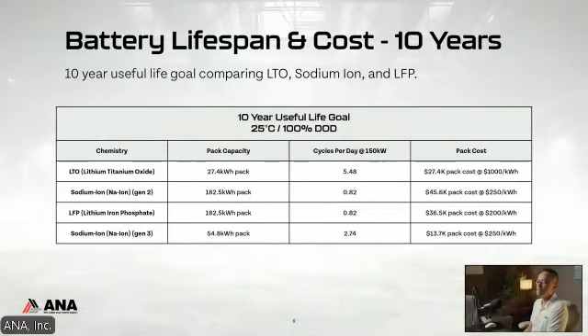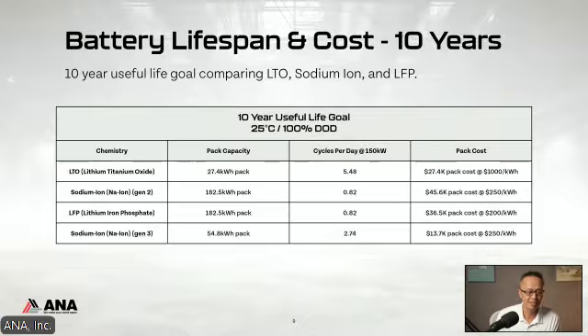In this chart, we're going to look at the battery lifespan and cost for an application where you need this system to run for 10 years. For that 50 kilowatt hour LTO pack, I think it said 18 years on the previous slide. So if you only need it to last 10 years, that means your battery pack needs to be only 27.4 kilowatt hours, okay? That means you're going to be cycling it about 5.5 times a day. Therefore, your total pack cost for this 27 kilowatt hour pack is going to be about $27,000, okay?